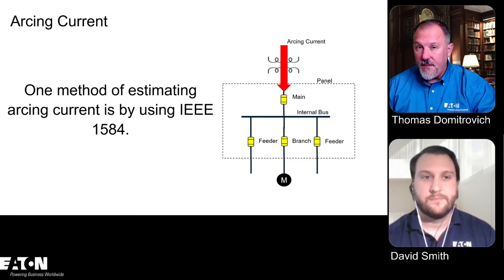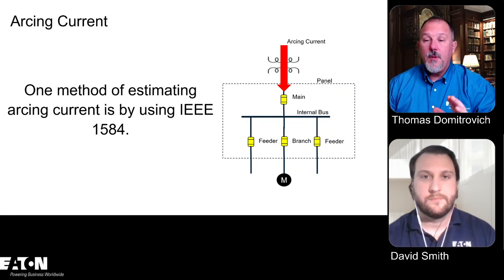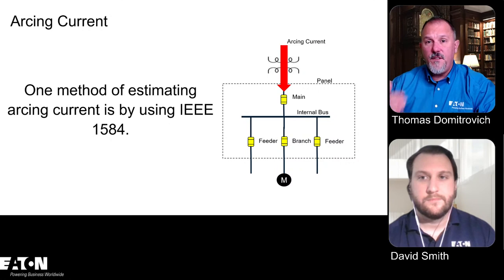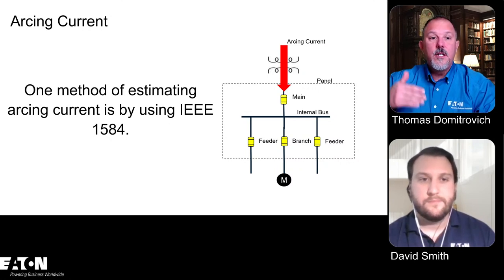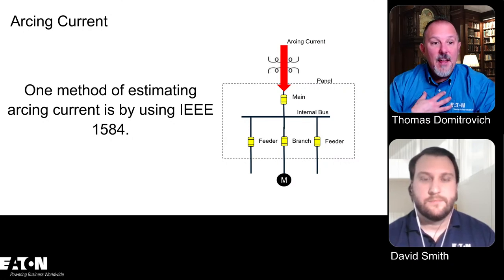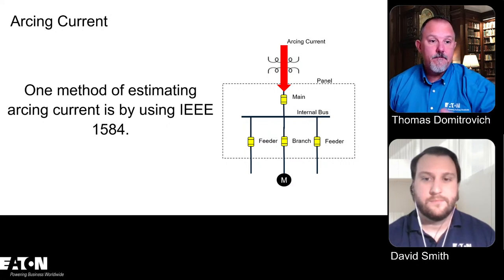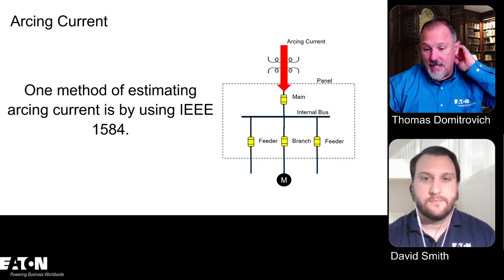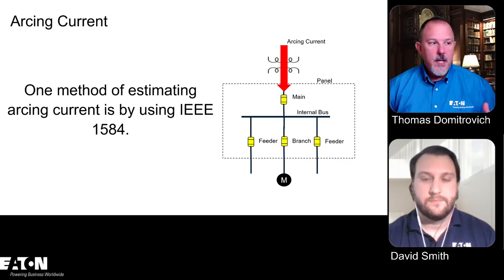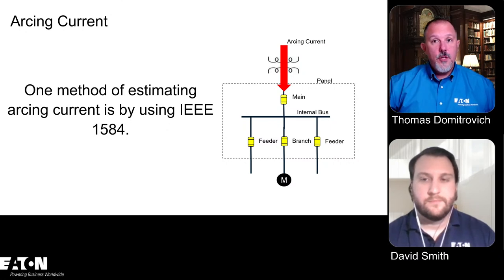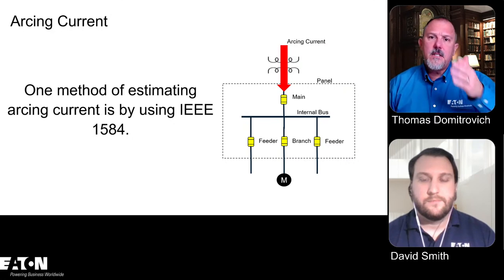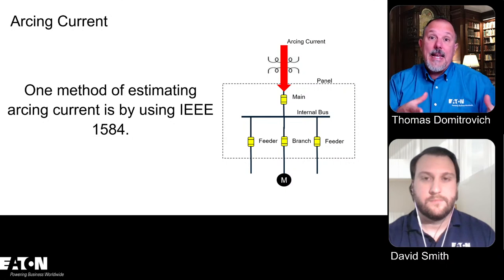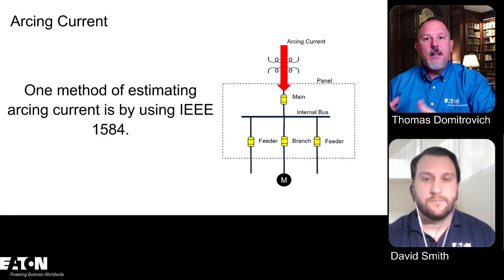The limitation of IEEE 1584 is 106,000 amps. We did not do any testing beyond 106,000 amps. So if you have 150,000 amps available, there is no method to calculate arcing current in existence. I thought it was the Ralph Lee method. Because everybody I asked, I said, what do you do when you're at 150,000 amps? And 1584 says, we use the Ralph Lee method. 70E recognizes the Ralph Lee method. I asked power system engineers, even in our group, what do you do? Well, SKM automatically uses the Ralph Lee method, and they'll tell you that.